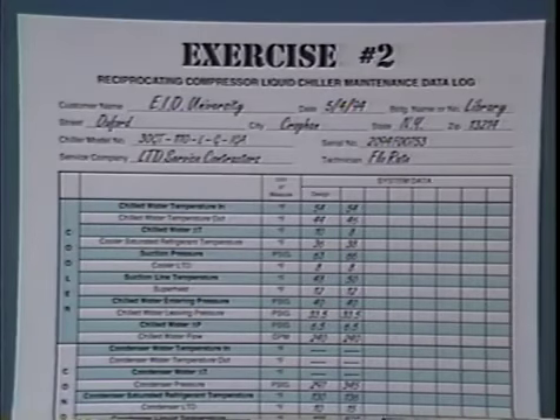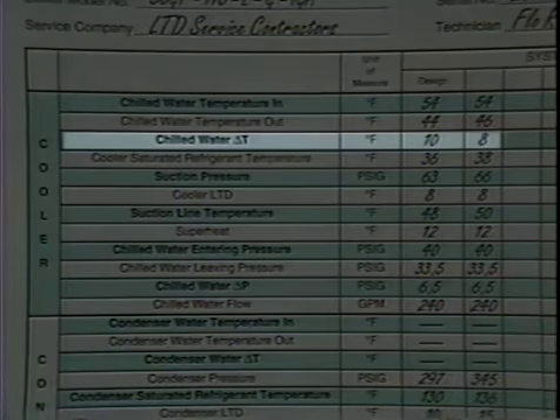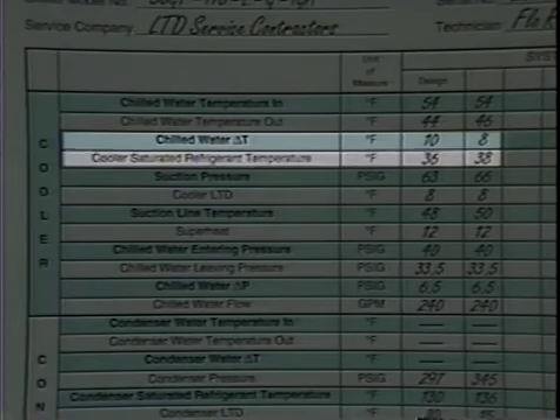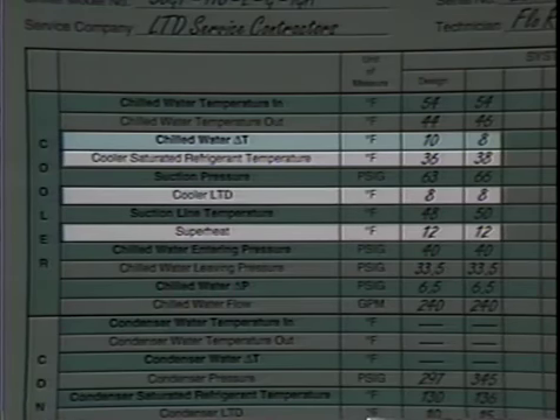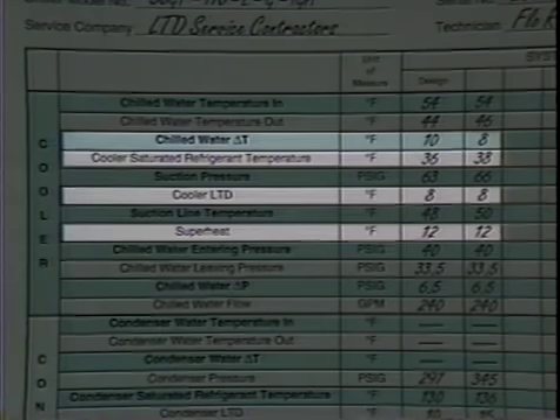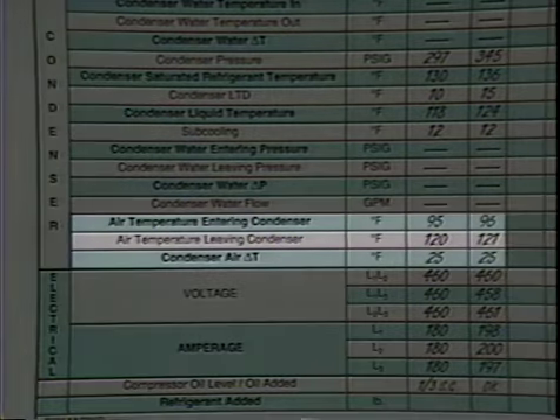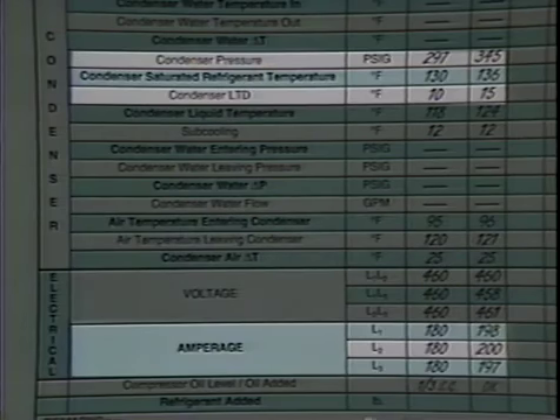Now let's see how you've done on this exercise. The chilled water delta T is 2 degrees Fahrenheit low, confirming low system capacity. The saturated cooler temperature is 2 degrees high, and the superheat is normal. The LTD is also normal, indicating no resistance to heat transfer. Since the cooler LTD is normal, we need to look at the condenser. Looking at the condenser data, we see the condenser air temperatures are near design conditions. However, the condensing pressure and temperature, LTD and chiller amperage, are higher than design. These data trends point to the condenser as the problem, so we need to look further.